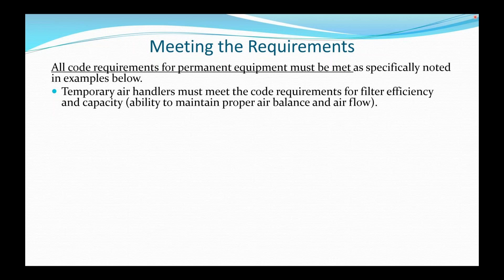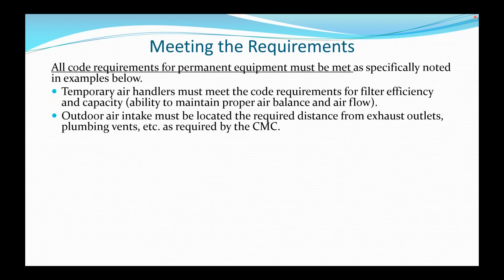And we'll start with temporary air handlers must meet the code requirements for filter efficiency and capacity. You must be able to maintain proper air balance and airflows. Outdoor intakes must still be located the required distance from the exhaust outlets, plumbing vents, etc., as required by the mechanical code. Temporary generator or temporary automatic transfer switch for emergency power supply must be sized to provide adequate capacity to meet the demand of operation for all functions and equipment to be served by each branch.